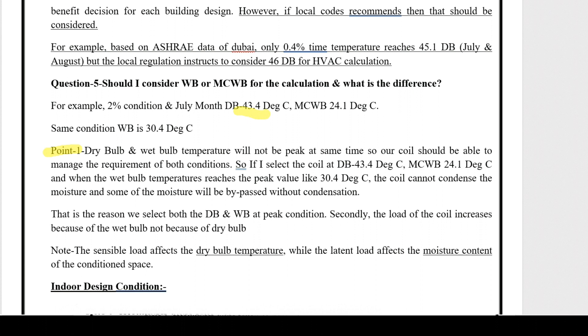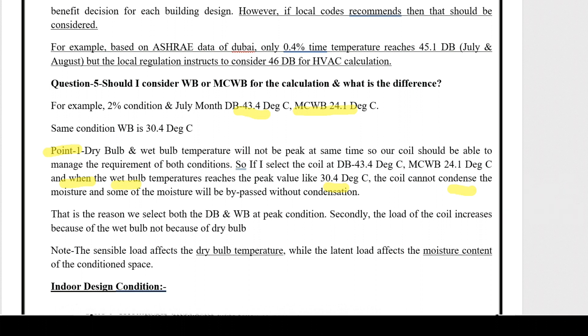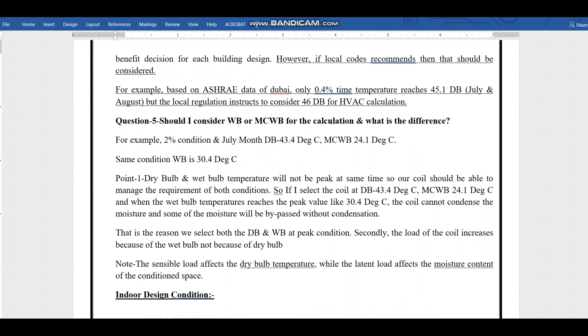If we select the coil at a dry bulb of 43.4°C with mean coincident wet bulb of 24.1°C, then when the wet bulb reaches its peak value of 30.4°C, the coil cannot condense — some moisture will bypass without condensation. That's the reason we select the design dry bulb and design wet bulb at their peak conditions. The sensible load is affected by dry bulb temperature, and the latent load is affected by moisture content. This is why we select the design wet bulb rather than the mean coincident wet bulb.